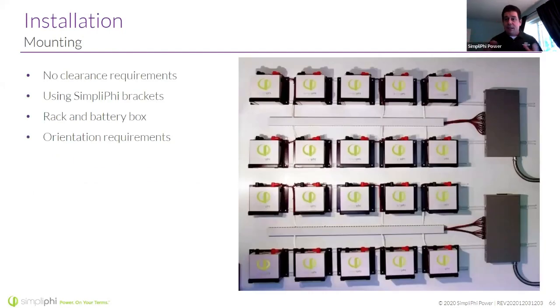When installing, because we don't have deflagration radius requirements, there are no clearance requirements. You can put the batteries next to each other, use brackets, or put them in a box. Really, the only thing we don't want you doing is putting them upside down - that can put the weight of the batteries on the BMS, and that's not a good thing. Obviously you'll want to consider humidity, and we have an entire presentation on harsh environments, temperature control, and so forth.